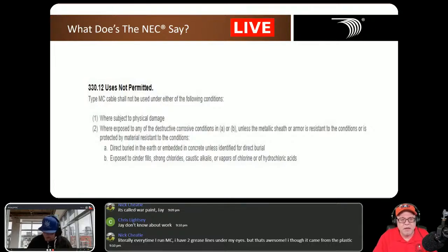So what are we saying here? If I can install it in the earth, what does condition A say? The first rule says you can't put it in locations for conditions A or B unless it's protected by material resistant to those conditions. Condition A says you can't direct bury it in the earth or embed it in concrete unless it's identified for direct burial. PVC jacketed MC is rated for direct bury, so it can be in contact with the earth, go in the earth, and also be embedded in concrete, as long as it's marked for direct burial.